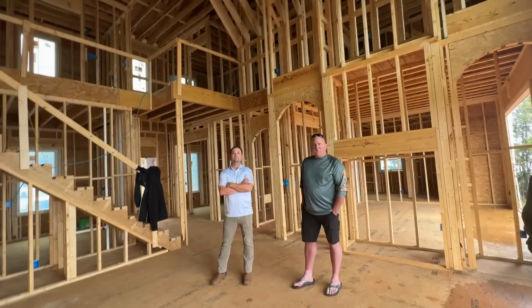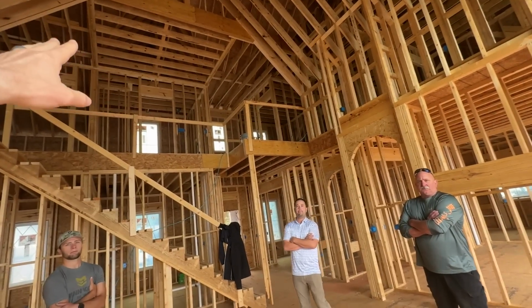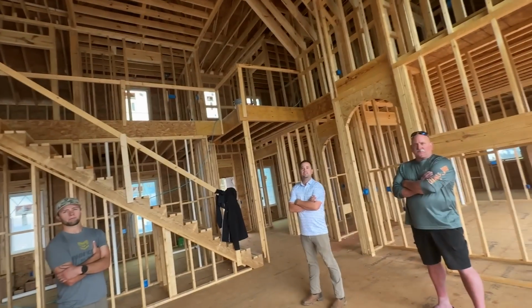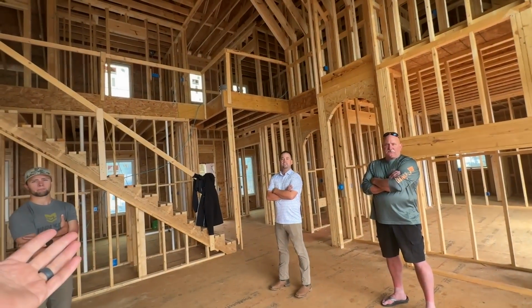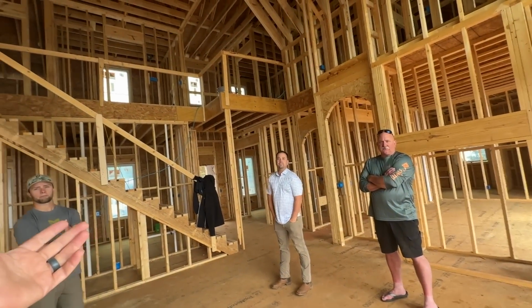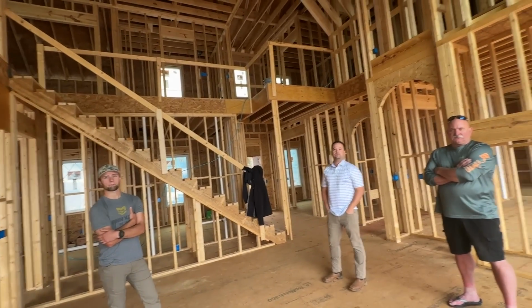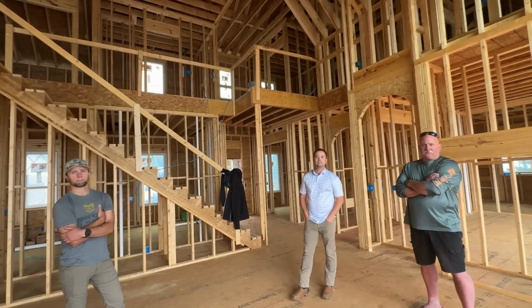Yeah, the Manual J would be great to do on this house because if code is 5 or 6 inches of insulation, the Manual J would be able to tell you, okay, with that amount of insulation at the roof line, here's the type of heating and cooling system you'd need. Let's say you need 6 tons to cool this house, and we need 70,000 BTUs of heat, let's say, to heat it, depending on the conditions of where you are.